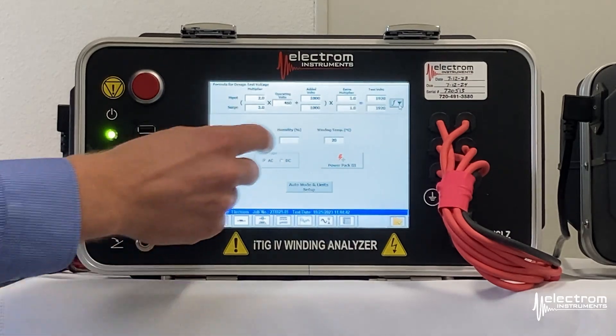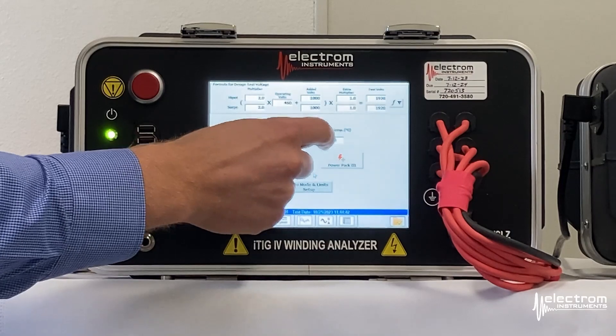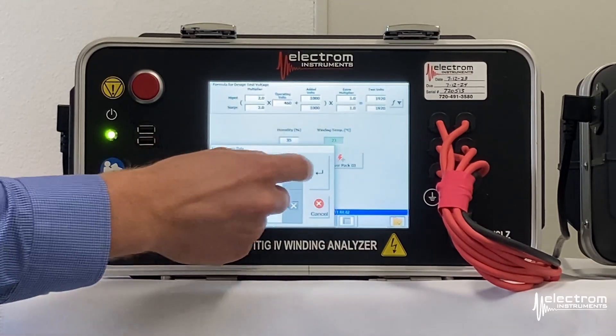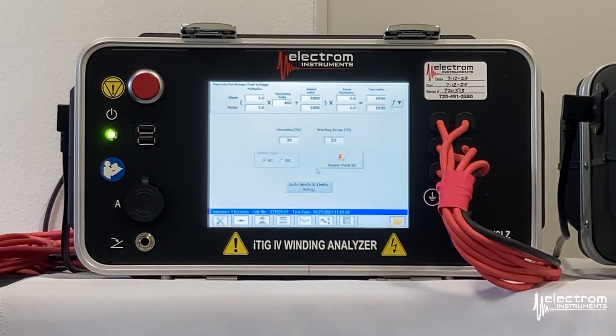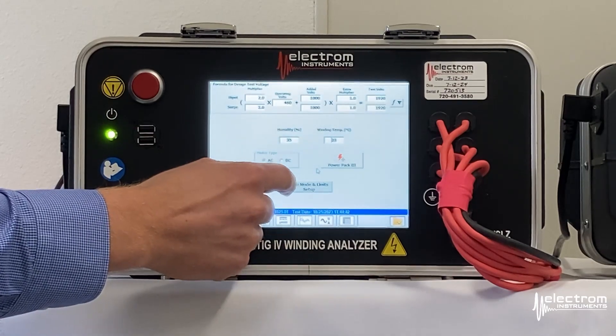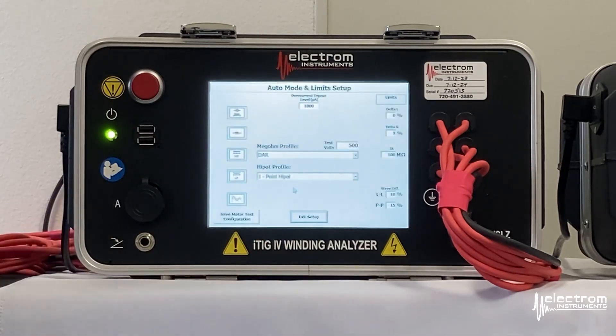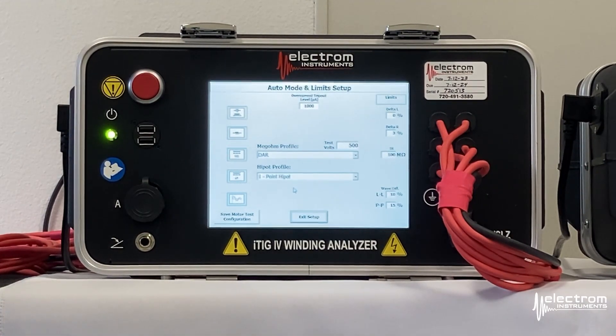We can enter in the humidity. We can also enter in the winding temperature. The winding temperature will be used to correct both the winding resistance measurement and the megaohm or insulation resistance measurement. Finally, we have the auto mode and limit setup screen, where we define the pass/fail criteria for this motor as well as which test profiles we want to use for megaohm and hypot.